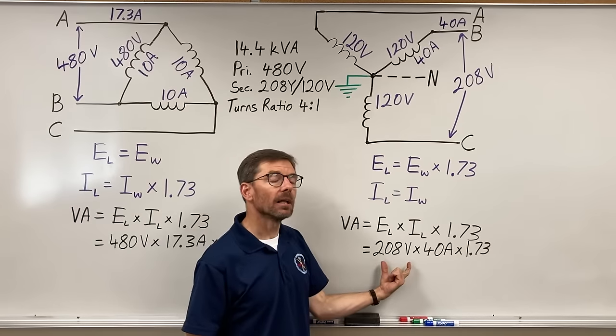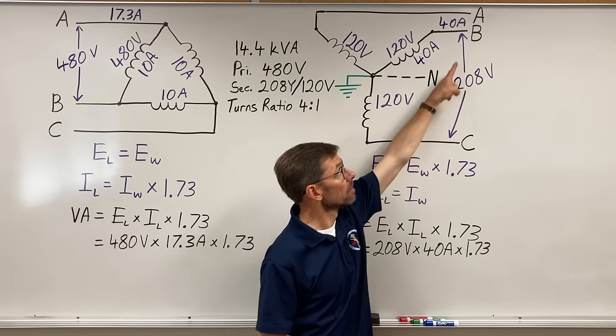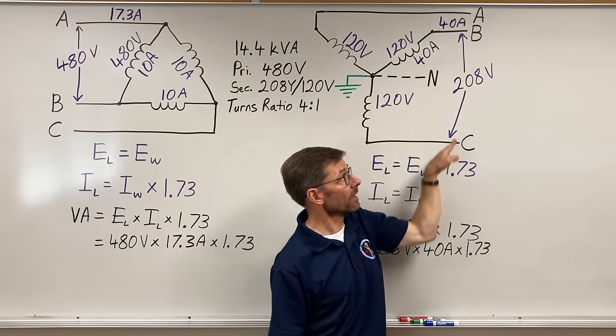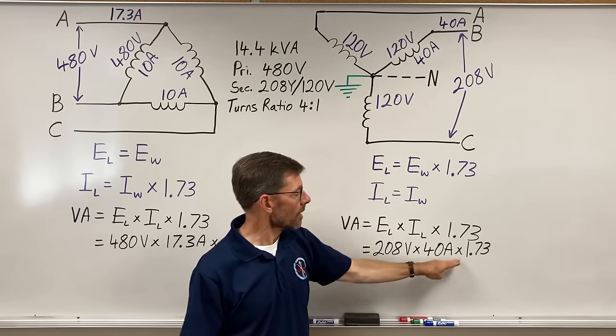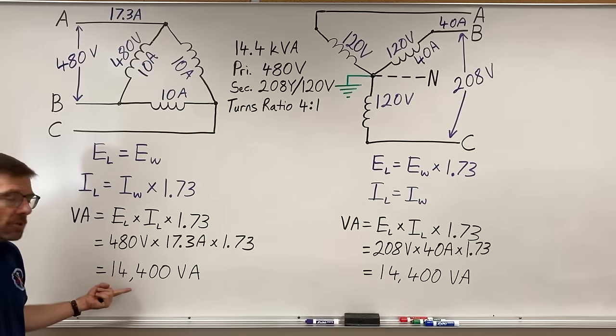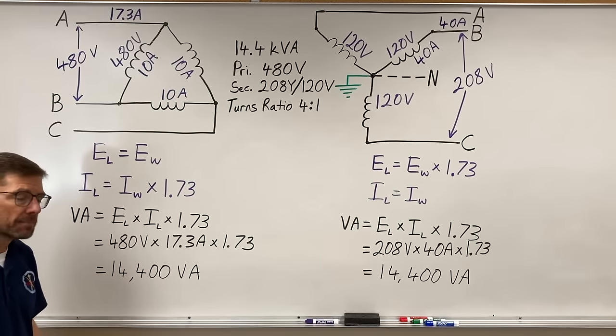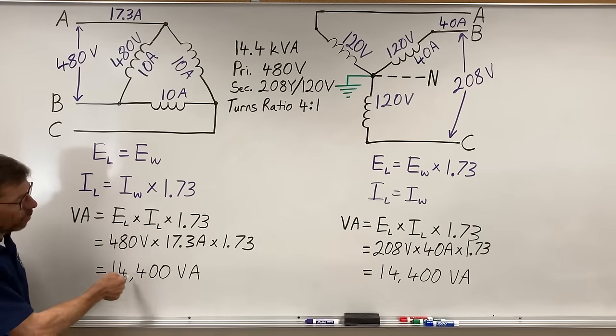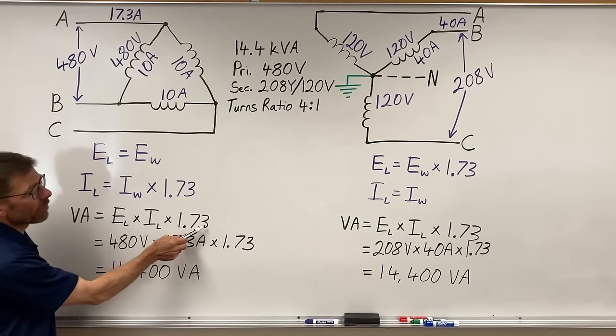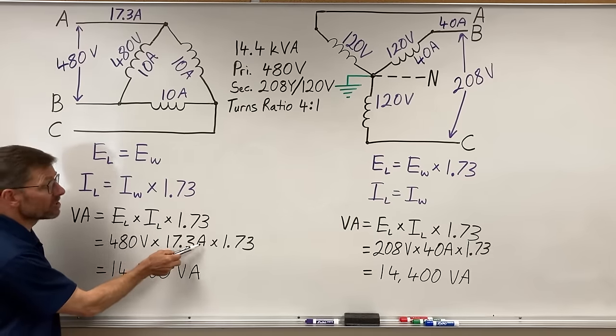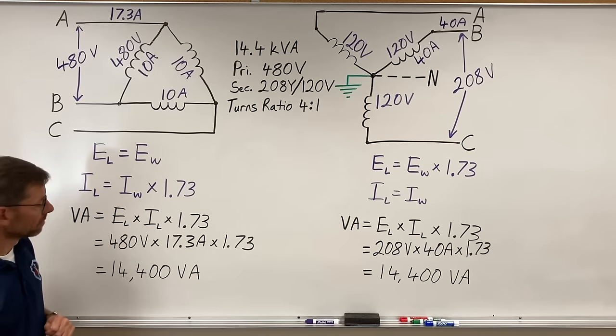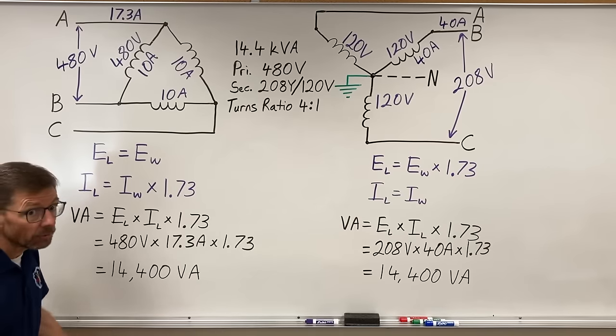So in the Y, I pick the line voltage, the larger voltage, times line amperage. Same 40 and 40, but I take the number from the line. Times 1.73. And they both equal 14,400 volt amps. Or thereabouts. Within rounding. Because this is technically square root of 3. So it'd be 1.732. Or 17.32. So you'll be within rounding of 14,400 volt amps. And if I turn that into kilo volt amps, thousands of volt amps, well, it's 14.4 thousand. 14.4 kVA.